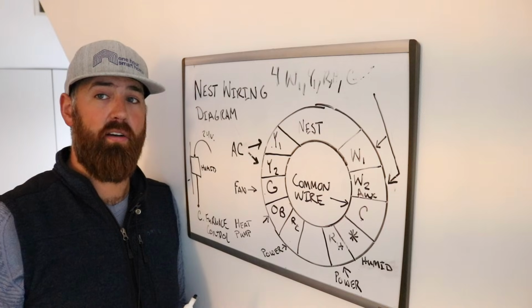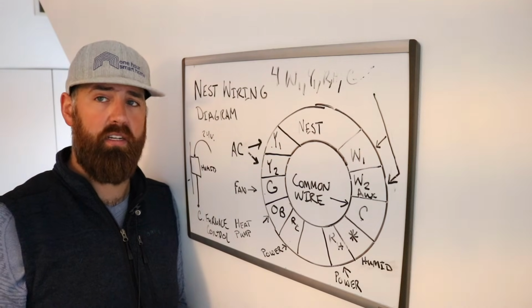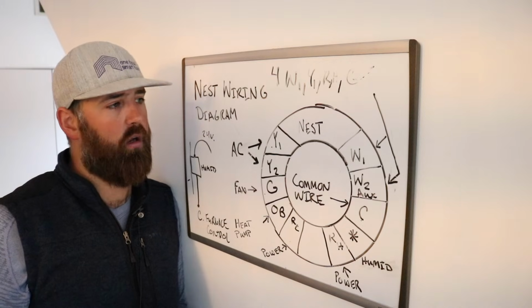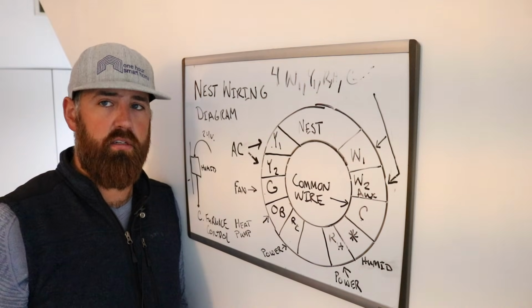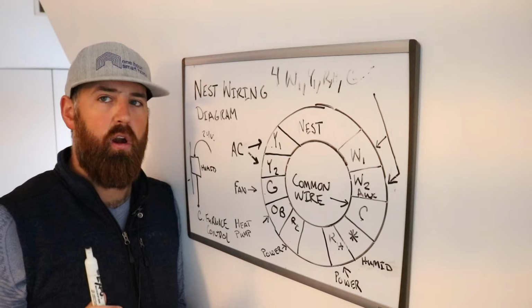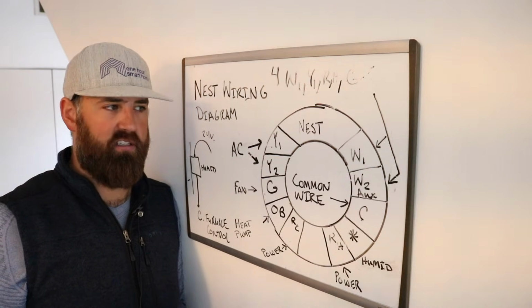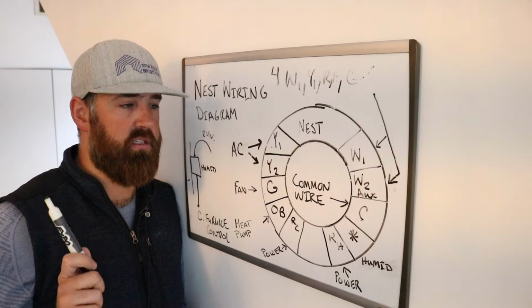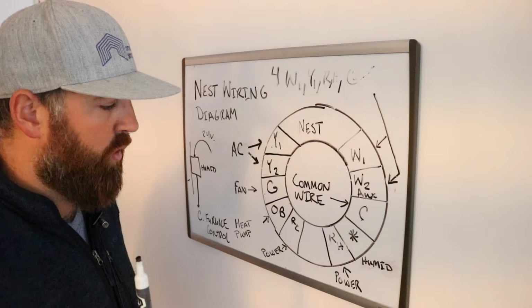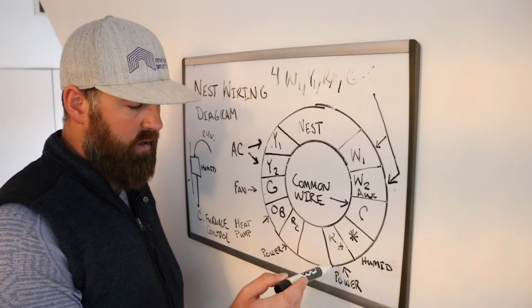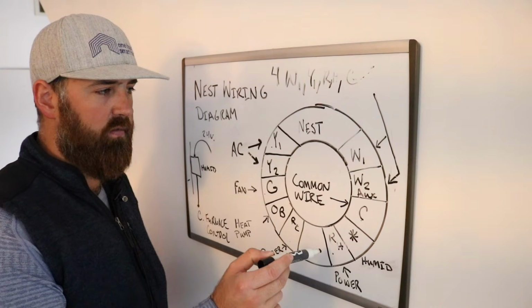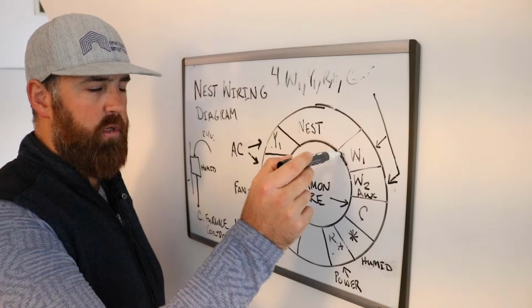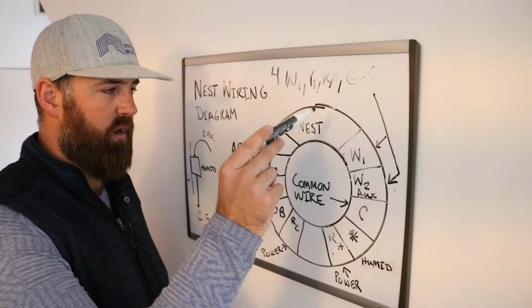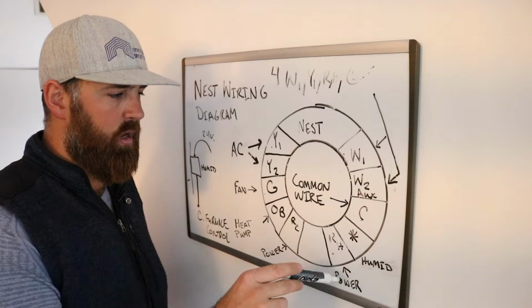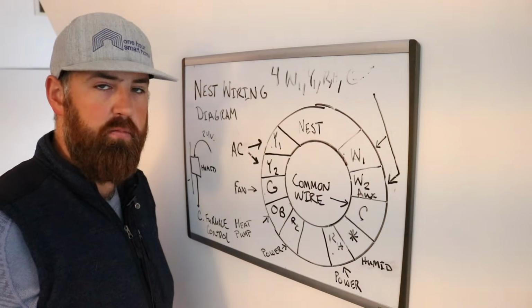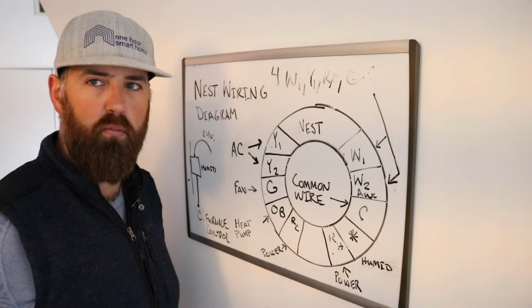Now, what about a 2-wire Nest thermostat? It does work in a lot of cases, for a couple specific situations. Let's say you have a boiler and want to add a Nest thermostat to it. You can do that most of the time because they put out enough power. For a boiler, all you'd have is your RH, your power coming in from the boiler, and W1 for heating. When the thermostat detects you need to turn on the boiler, it completes this circuit and W1 activates, and your boiler works.